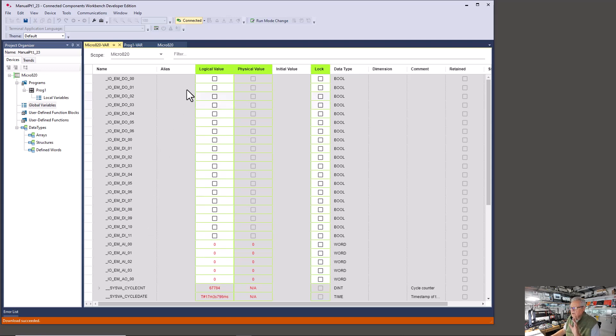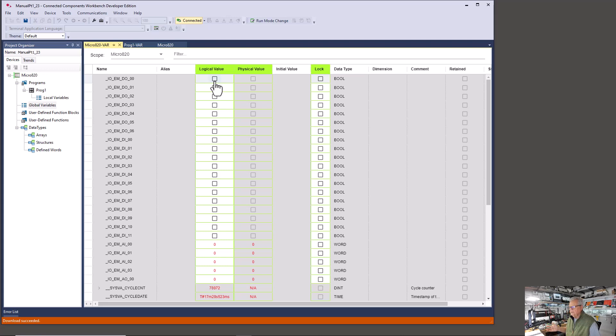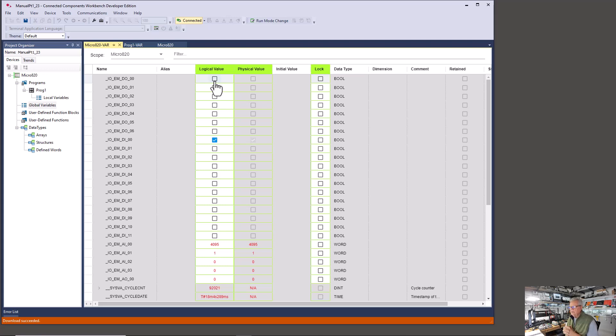Notice up here I have 'Logical Value' and 'Physical Value.' If we look at the Micro 820 we can see we're in run mode. The logical value is the value in the logic, but we don't have any ladder logic, so these logical values should stay at zero. Now since we're running I'm going to turn on an input. Notice when I did, I got a check mark. This isn't a box you check — it's showing you the logical value of digital input zero. IO embedded digital input zero is just a bit in memory — it's a Boolean. I could actually force that value, but I don't suggest doing that.